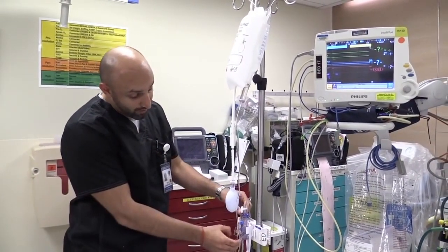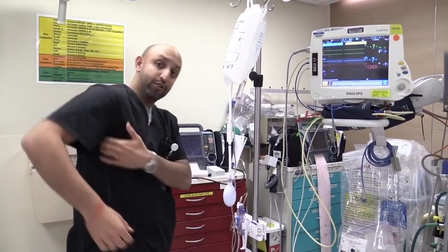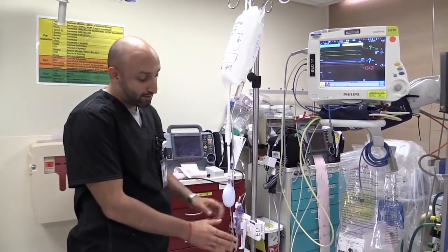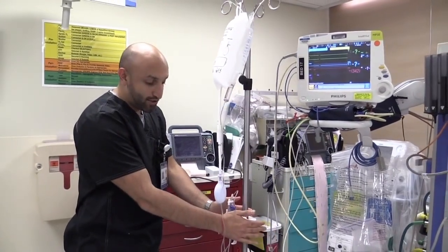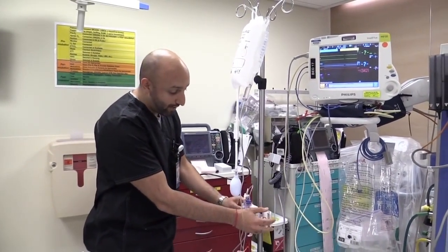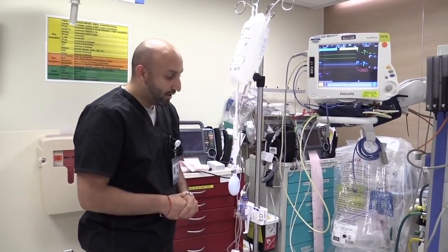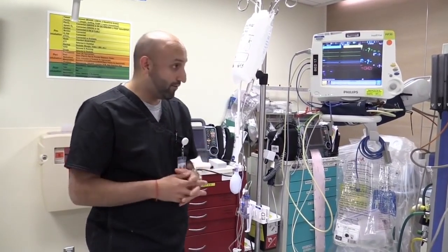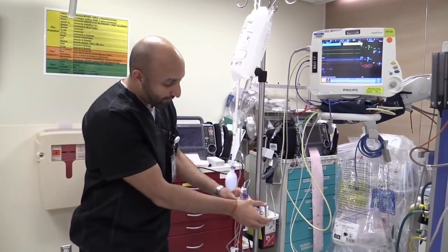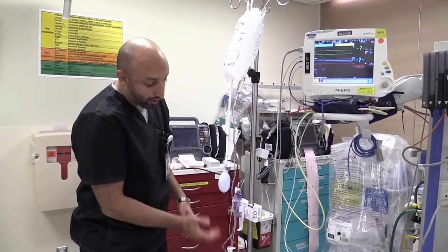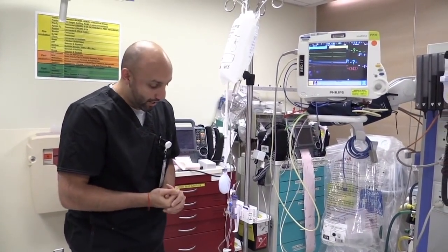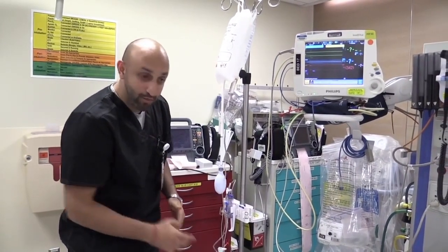Using some older systems, some people would actually tape the transducer to the patient's sides, but if you have this system, it's probably much easier to keep it attached to the stand over here. But you want to make sure that that height is correct. So if you have a dampened wave, you're going to check your bag. You're going to make sure the height is okay on this, make sure all the air bubbles are out as well, and make sure there's no kinks in the tubing either.